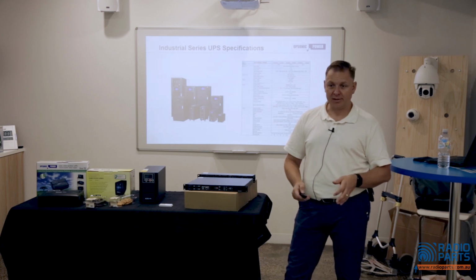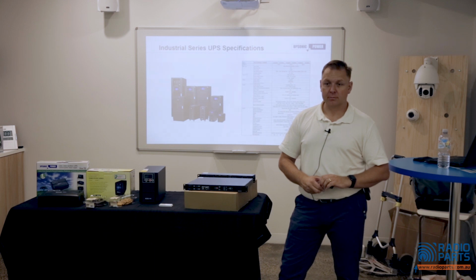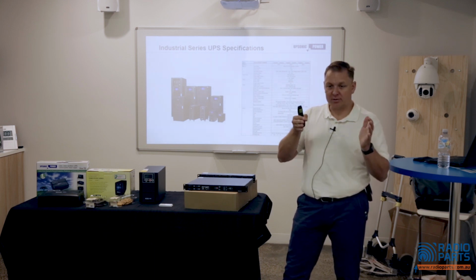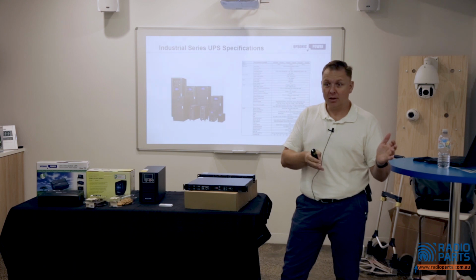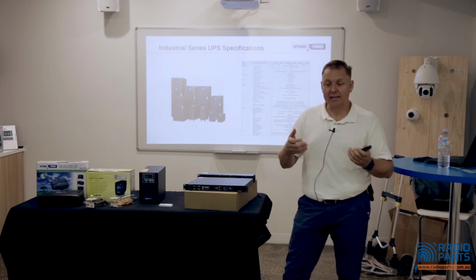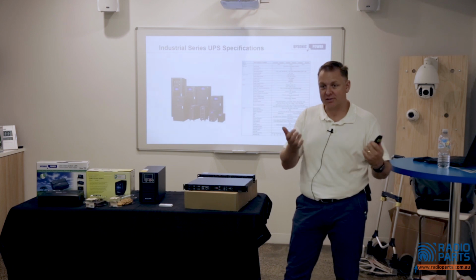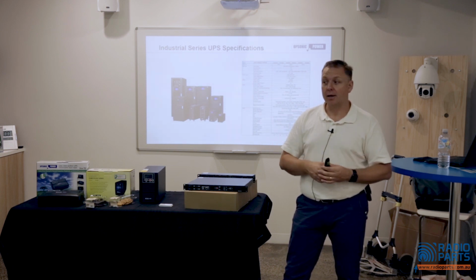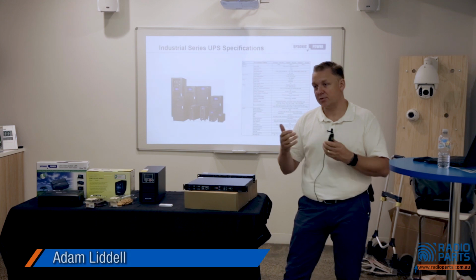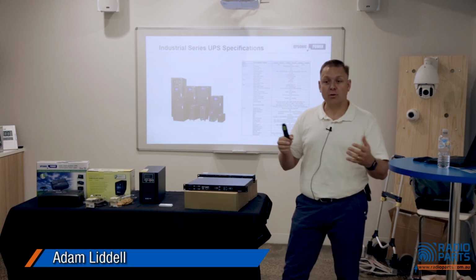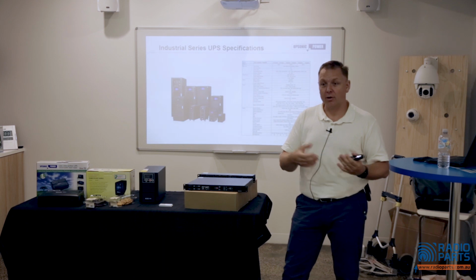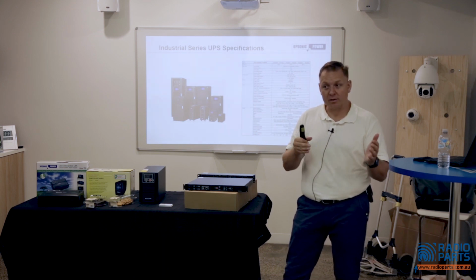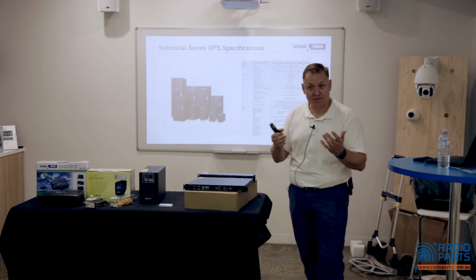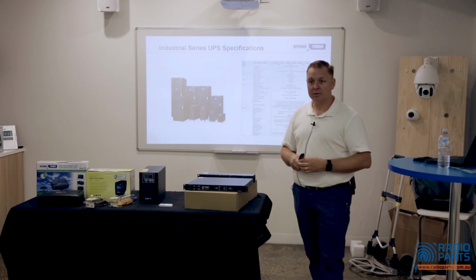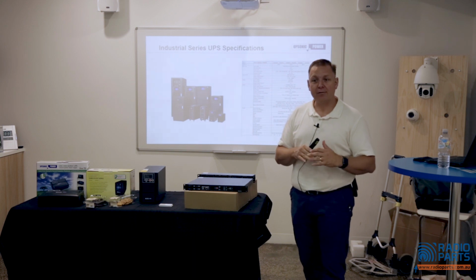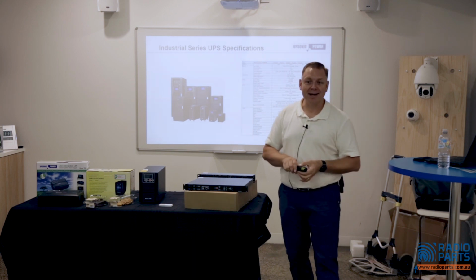A full dual conversion UPS will be fine with it. If the load goes down to basically nothing, the UPS will still sit there running, still consuming its own power because it's still running itself - the inverter's still clocked, and it's trickle charging the batteries. All of that happens, and as soon as the load comes back on, it's fine, as long as inrush current is accounted for, if pumps or something are starting - that's an important consideration. If that's met for their tomatoes or whatever they're growing, that's fine.